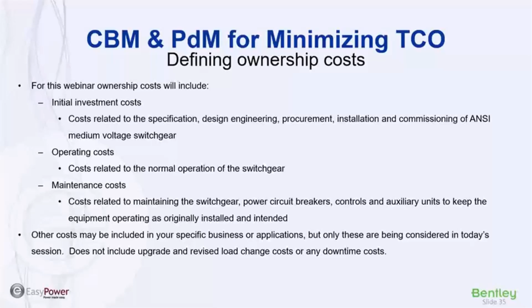So what I'm going to do is just show an example. So here's a lineup of switchgear, 15 kV, 3000 amp. It's a main-tie-main configuration, right? Non-arc-resistant switchgear. We will look at different technologies that can be applied that help us with the condition-based and predictive maintenance. These are just samples of technologies. There are many others, but you could essentially follow the same principle to evaluate the effectiveness of those technologies to help you reduce the total cost of ownership. Right? So what I'll cover here is basically four things: magnetically actuated breakers, current and voltage sensors, digital communication, and asset health monitoring.